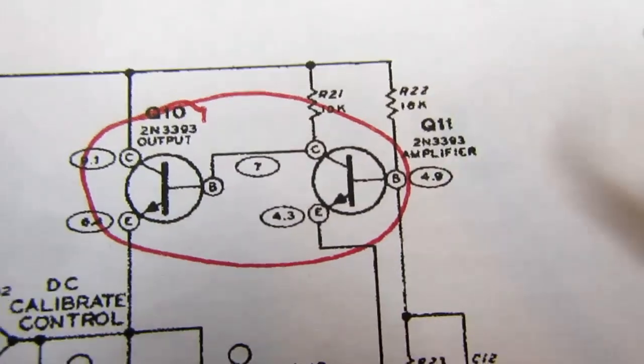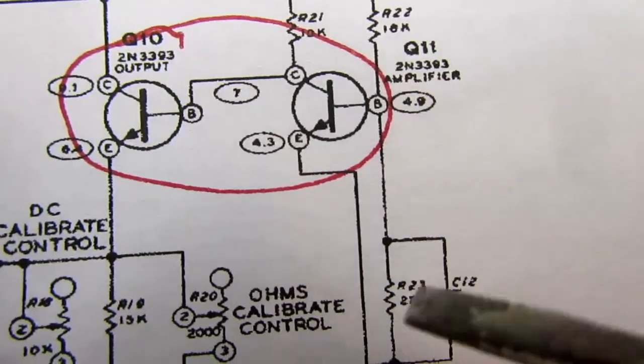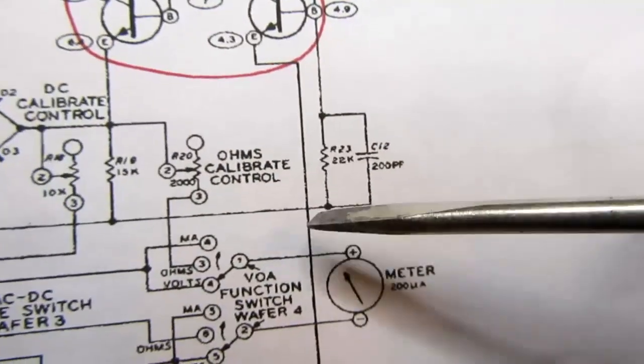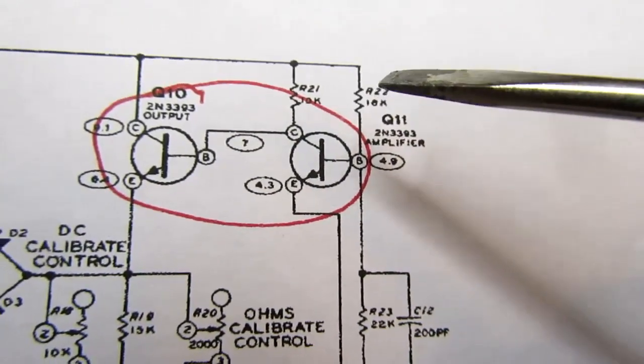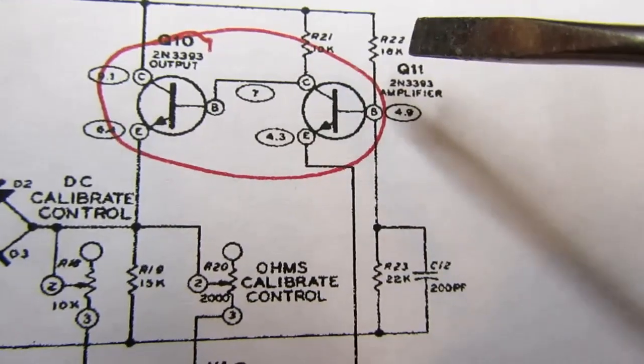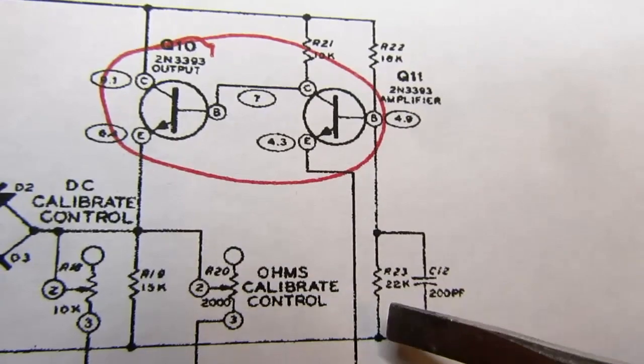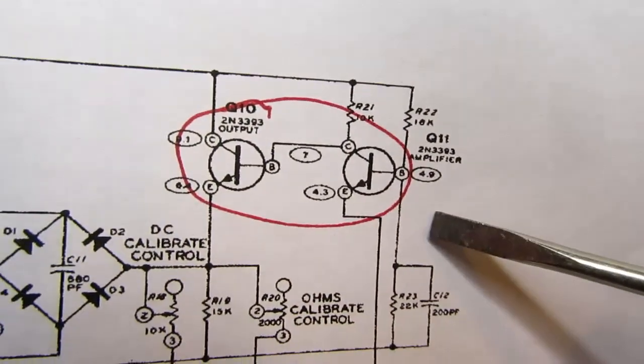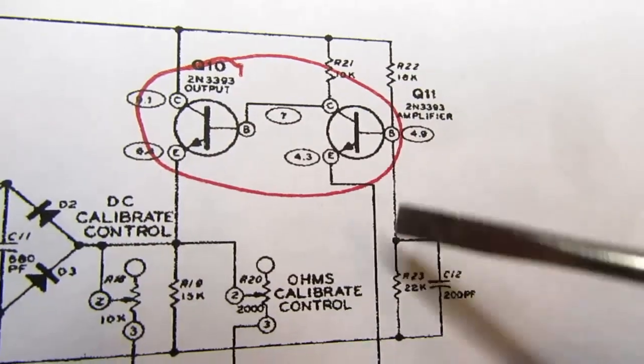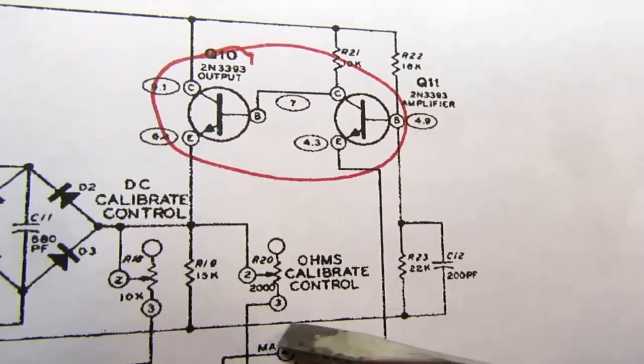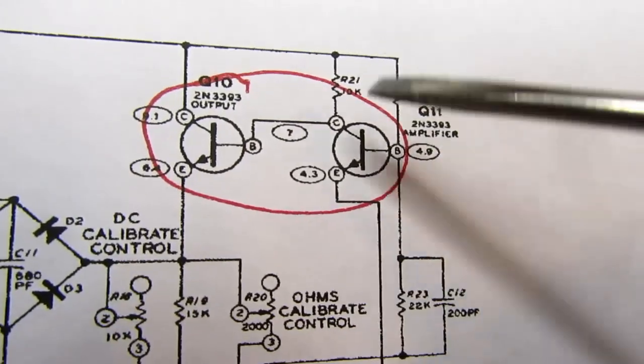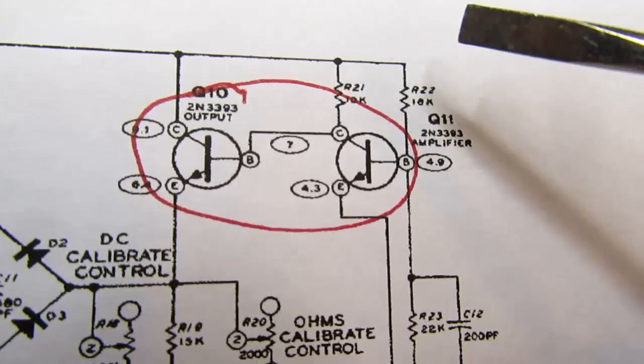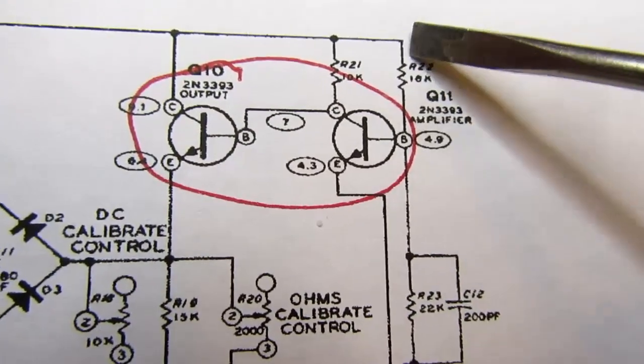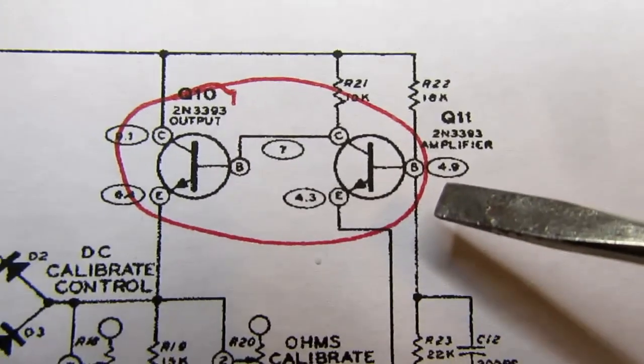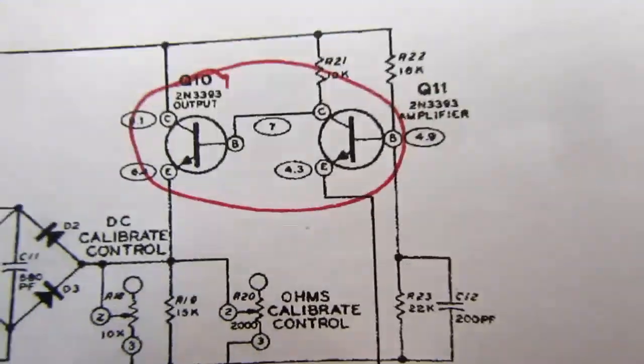And on this side, the input to the bridge is a 18K over a 22K connected between B plus and B minus. That's essentially the battery voltage, or the output of the internal battery eliminator. It's 18 volts from there to, I'm sorry, it's 18 volts from the battery. It's 9.1 volts from here to here. So if you consider the circuit common to be your measurement reference point, then this would be 9.1 volts. So this just forms a voltage divider, 18K over 22K, and it should always be at 4.9 volts or something pretty close to it. This particular meter in front of me, it wants to sit at 5.1 volts.